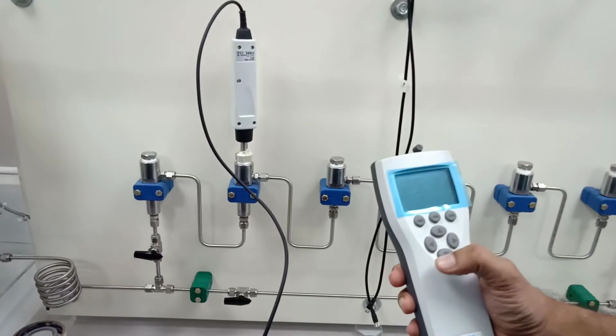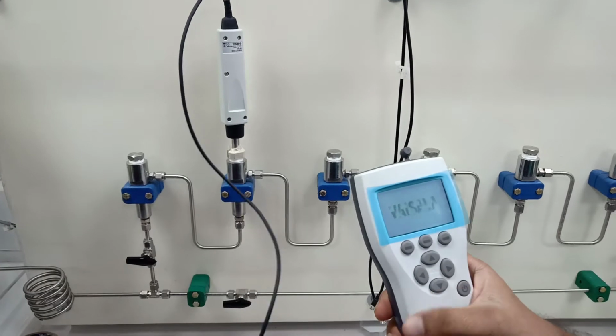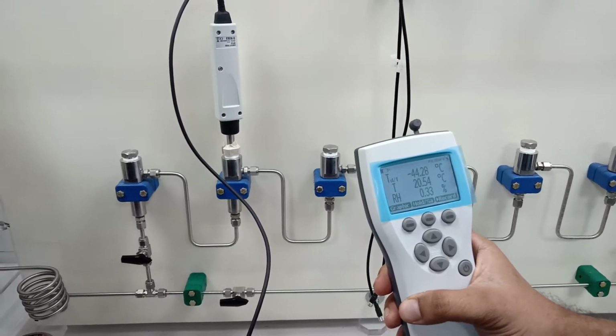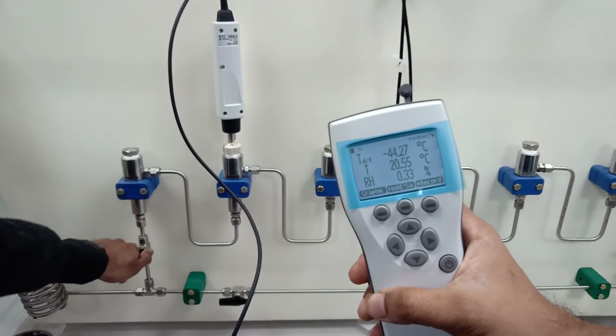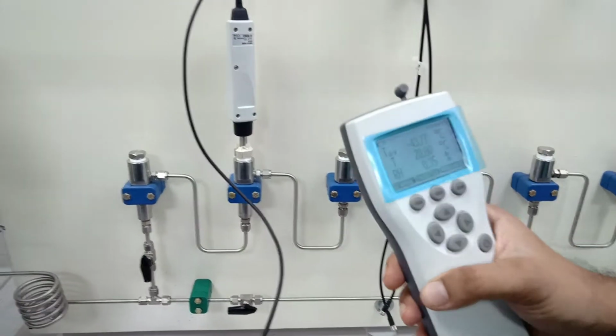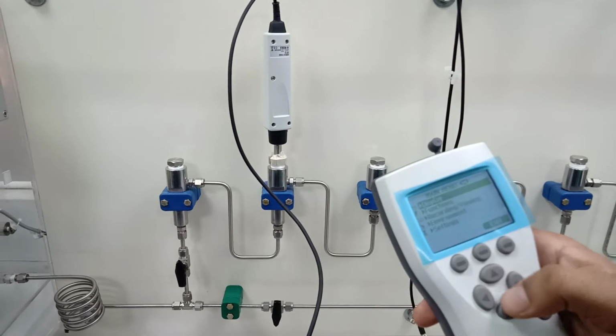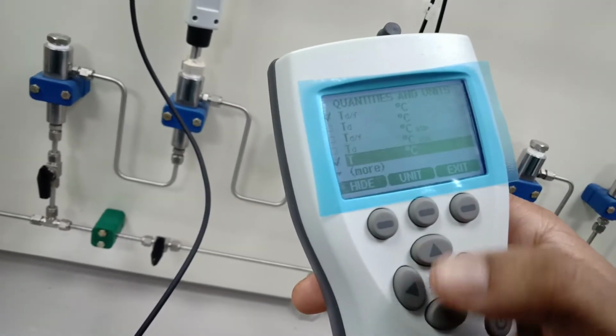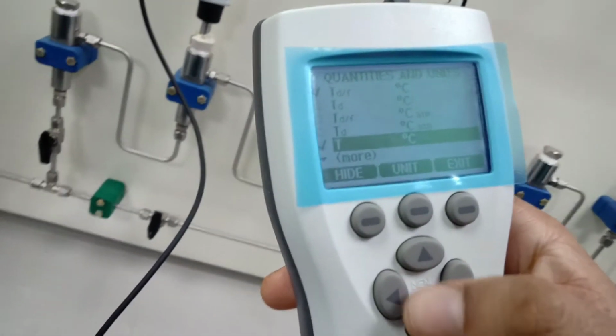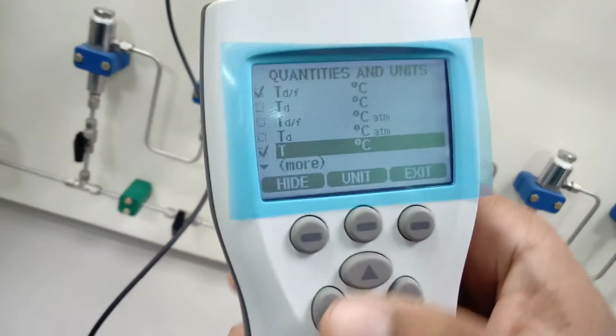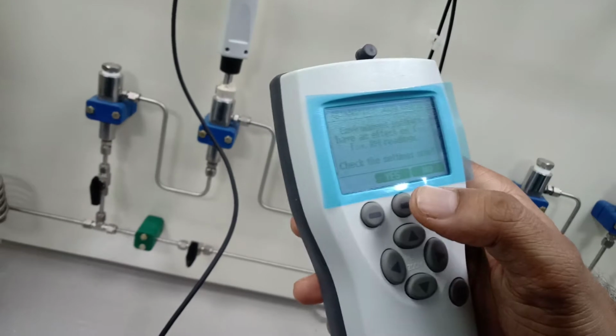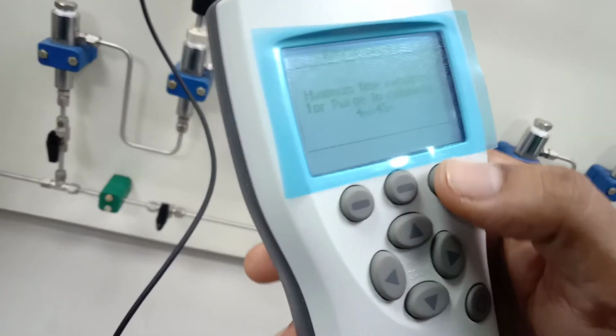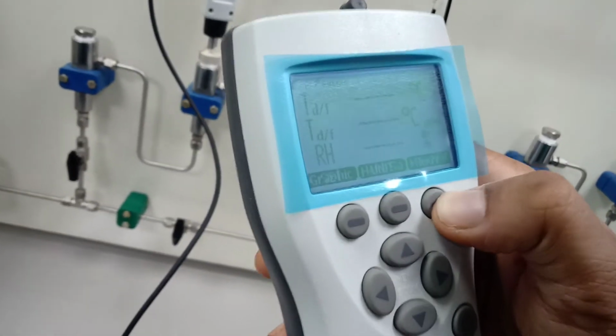And now we'll show you the dew point in a process. This is the setup in which we are measuring the dew point. Switch on the indicator. So it is showing the dew point minus 44.25 degrees C. So in GIS, the main thing is you measure the dew point at atmospheric pressure. So what I can do is I will go to the menu, display. For selecting atmospheric dew point, I have to unselect one of the parameter. So right now it has gone in this purging mode, which can be seen. I have to put the pressure as well. So here I have put 6 bar gauge pressure. Right now it is purging.